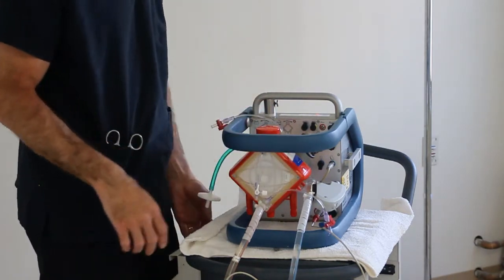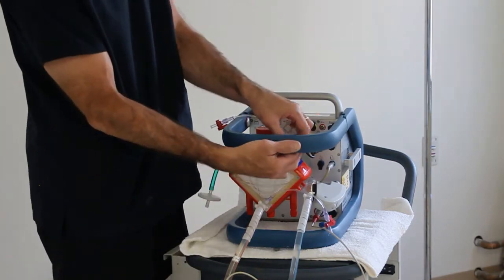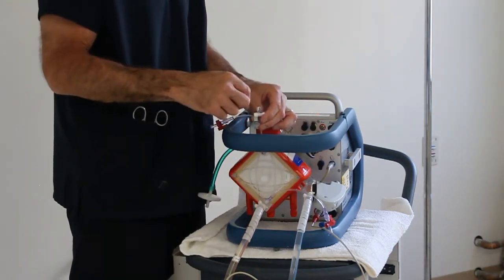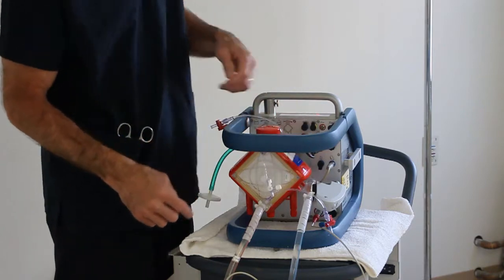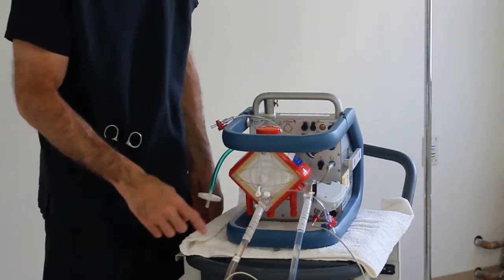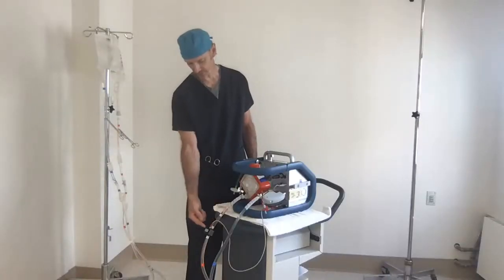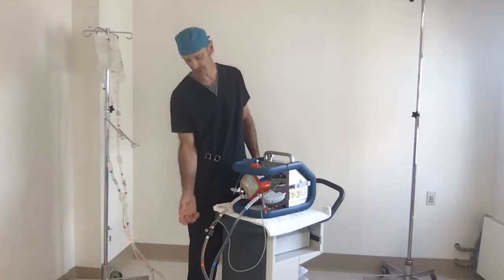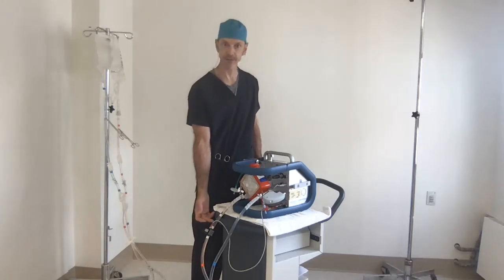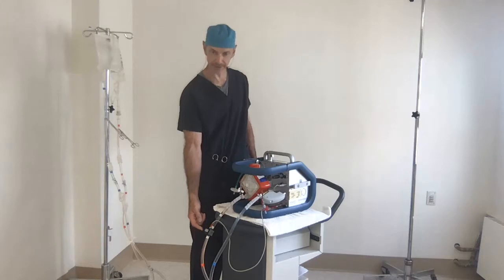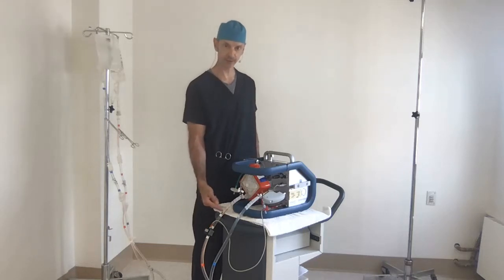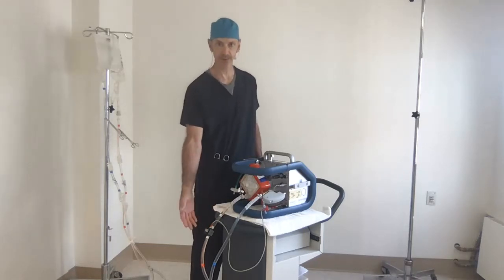All right, so 3 pigtails. And of course, these pigtails should have sterile caps on them. Keep this stuff clean. All right, the flow comes out. It goes past a flow probe right here in the prescribed place for you to put that flow probe between the 2 white lines just downstream of the clamp symbol. But of course, you could put that anywhere on the arterial line.